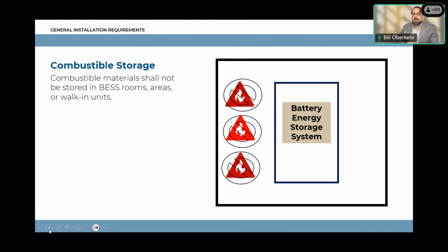This is a big one: combustible storage. Another one that should kind of be taken for granted, but unfortunately that's not always the case. We don't want to store combustible things near the energy storage system. As we saw on the graph from the Electric Power Research Institute, or EPRI, failures are very, very rare, happening in a fraction of a percentage of installations, a fraction of one incident per gigawatt hour of deployed capacity. That said, that's not never.